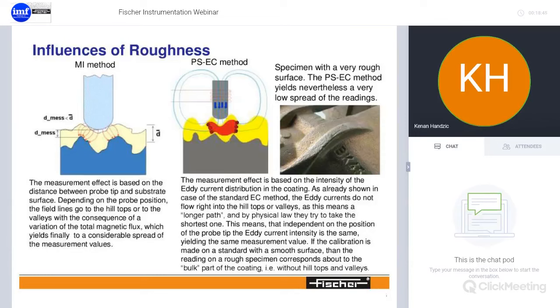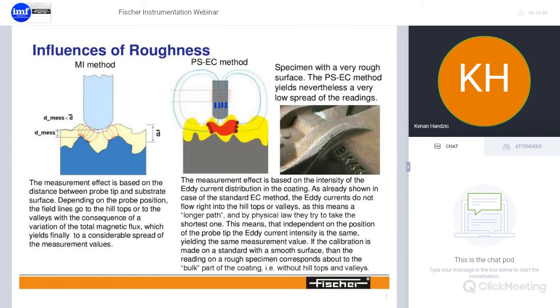The phase-sensitive eddy current method generates eddy currents that sit within the coating material — they do not fall into the pits nor sit solely on top of the peaks. What happens is that the average reading of the coating material is taken, not just at local minima and maxima. This method is ideal for rough substrates — for example when coating brake pads or brake calipers with zinc.